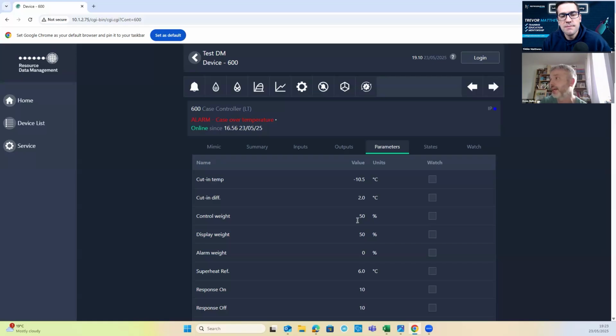You'll soon see, because when you're actually running and you've got a differential on your probes, if you set it the wrong way around, it's going to read exactly the same as the probe you don't want, but it will be relative to air on or air off, that one. If it's a case, go by what your case manufacturer is saying. If it's a really good case manufacturer, they may have set your case up for you. Don't always count on them having done that, because some of them won't have. If it's a cold store, you're going to be on your own.